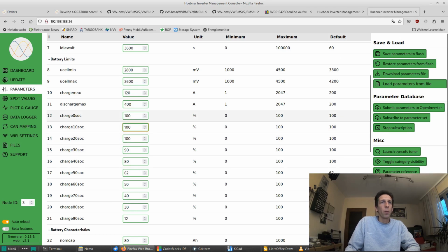Same as we did here: from 0 to 10% we allow 100% of this charge max. From 10 to 20 still 100%, 20 to 30 100%, and then we start tapering off - 90%, 80, and so on. These limits are just multiplied onto this charge curve.